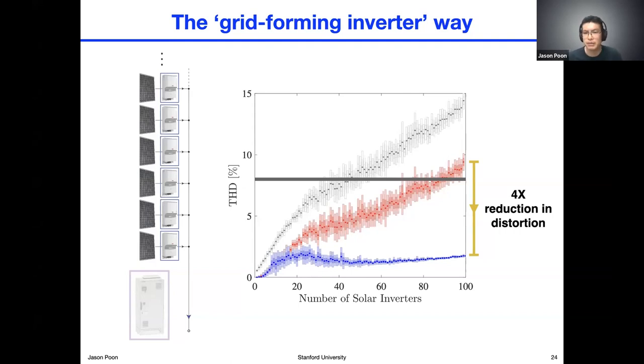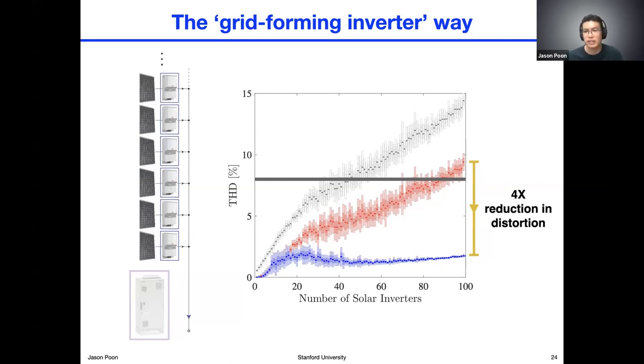What's very promising about this method is that even at very high numbers of inverters, we are still below the 8% limit set by IEEE 519. By using this method, the size of our system will no longer be constrained by the harmonics — at least we've checked off this one box that we no longer have to worry about in terms of distortion.